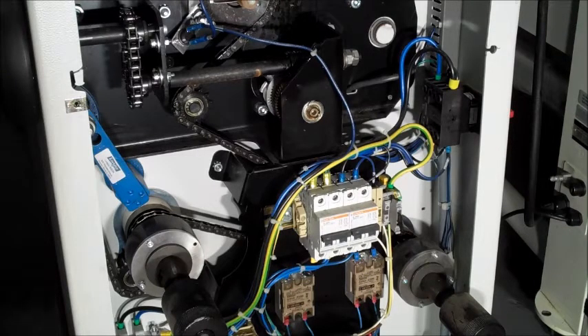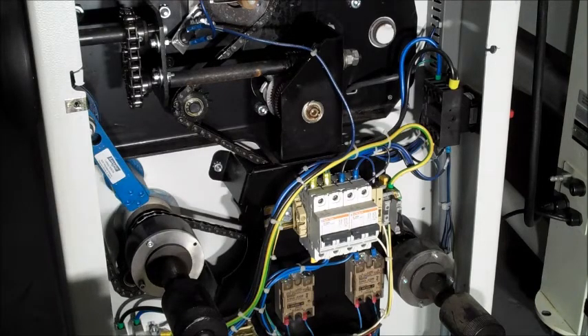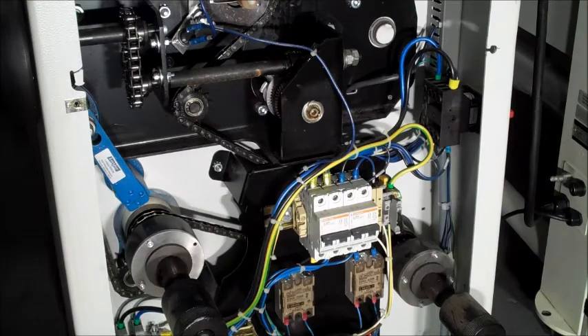Some of what you're going to see in the field as far as problems with your electrical system is going to be related to bad connections. Because these are high voltages and high amperage machines, if you get any loose connection, it's going to result in arcing and eventually losing power supply. So that's the most common thing.